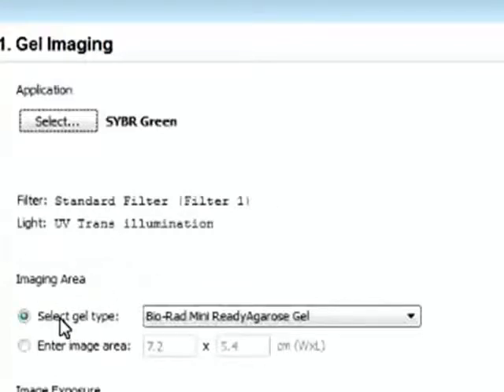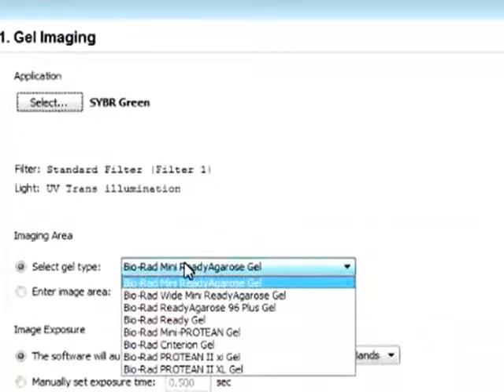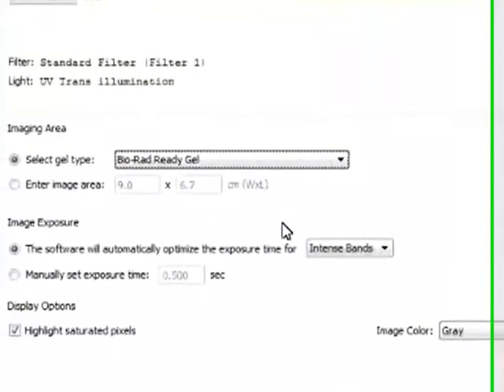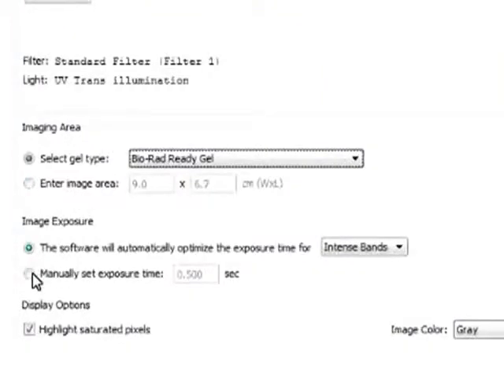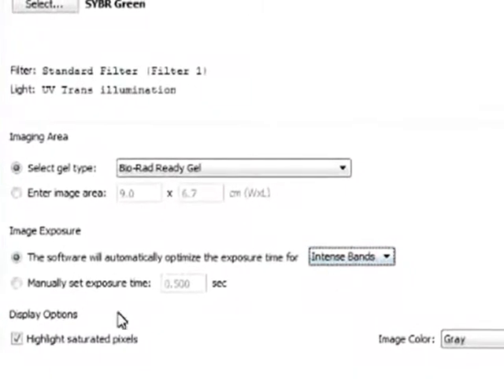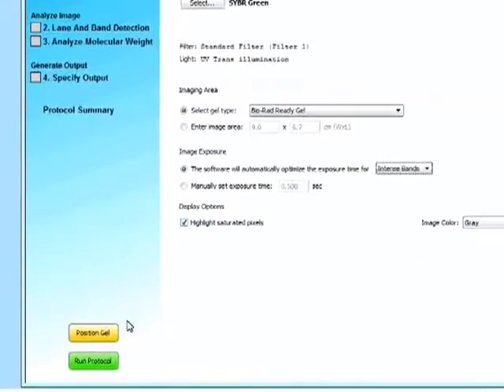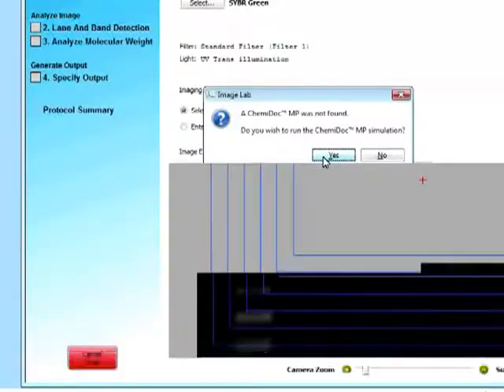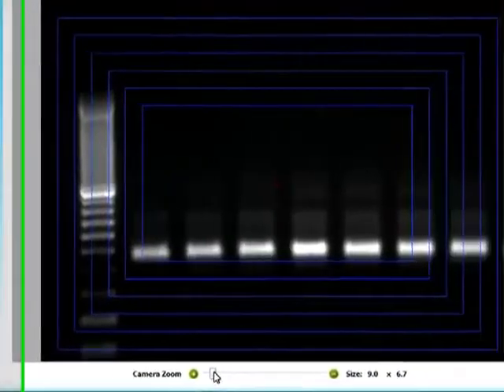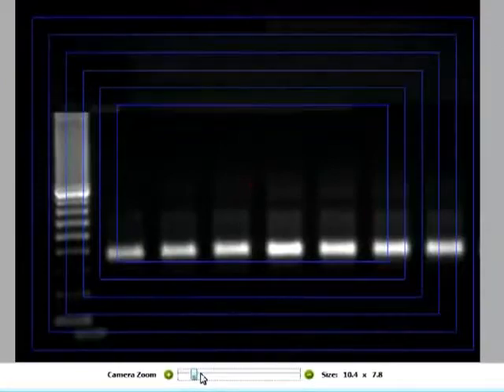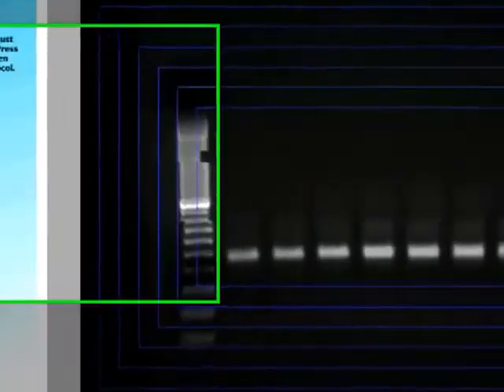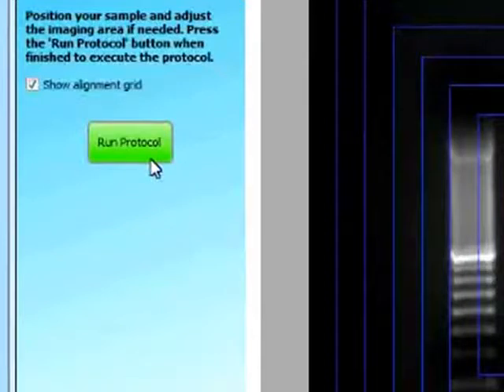Next, we can select the imaging area. So if we have purchased a specific BioRad gel, we can select it and you can see how the area changes. And we can also enter the imaging area. We can set the image exposure time either manually or automatically, looking at intense band or faint band. And we can select to highlight saturated pixels as well. So the next step is the position gel, and we can select to zoom in or out in here.